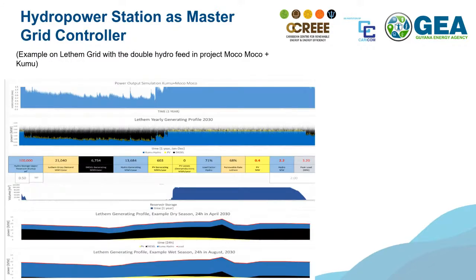This is the same Lethem system again, in a simulation, to give you a better overview. Here's the wet season - you see the hydro, the blue one, is really dominating. The black is just a small diesel, and the red is the PV. So if the hydro is dominating, it has to be the main controller in the grid, holding the voltage and frequency as master. In the dry season it's a bit different - the diesel is a little higher, so you may have to switch between diesel and hydro as the controller.